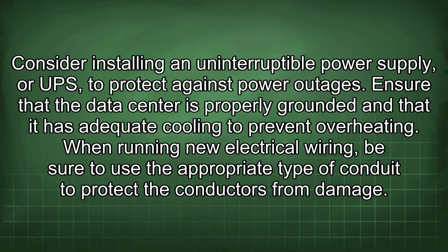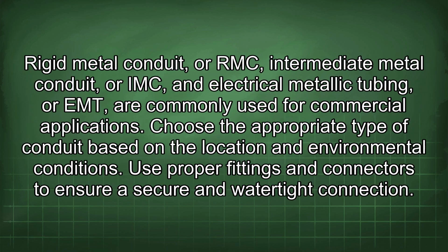When running new electrical wiring, be sure to use the appropriate type of conduit to protect the conductors from damage. Rigid metal conduit, or RMC, intermediate metal conduit, or IMC, and electrical metallic tubing, or EMT, are commonly used for commercial applications. Choose the appropriate type of conduit based on the location and environmental conditions. Use proper fittings and connectors to ensure a secure and watertight connection.